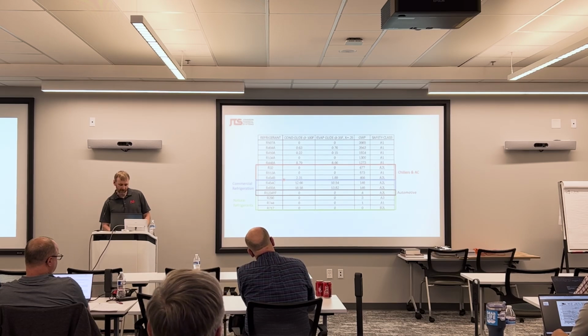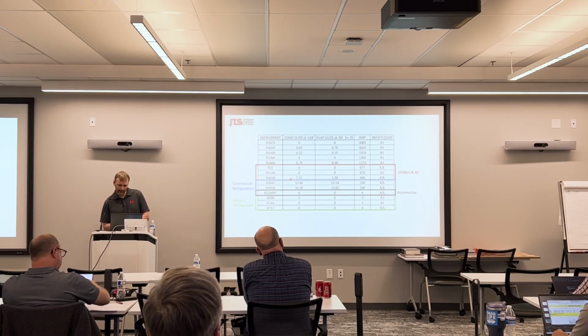R513A, it's a 500 series refrigerant, which means it's an azeotrope. 0 degrees of glide, 573 is its GWP. It's an A1 refrigerant, which is pretty cool, non-flammable. R454B is actually where JTS is looking. We're working with UL to get a UL listing on our chillers at the moment for R454B. It's got about 2 degrees of glide, 466 GWP, and it's an A2L refrigerant.